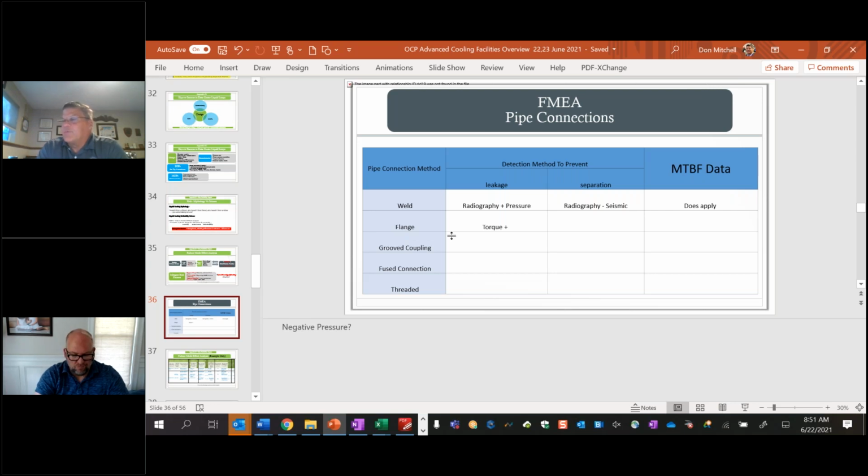And on board ship, we would pull into shipyards or pull back into the port, and we would end up connecting. But to your point, we never had flanges right over things that would leak or where leakage would cause damage. And if you did have flanges over things that could be damaged, then you put some sort of trays and leak detectors and other things to catch the minor amount of leakage from the flange. What I'm highlighting here is flanges can be very reliable, but they can be a big challenge if you don't contain them. Does that sound consistent with what you're saying, John?